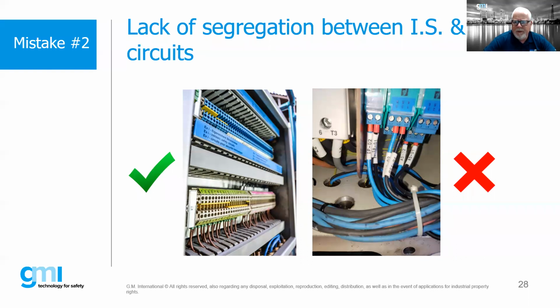The issue with this installation is that we had some circuits that were exiting the intrinsically safe associated apparatus and run down right below the contactor. And what you see there is going into a barrier gland, into a flame-proof box, and we have no segregation between, it looks like, the L1 connection there and our IS. So that gives the opportunity for inductive currents to enter into our IS system, and that's a big no-no.